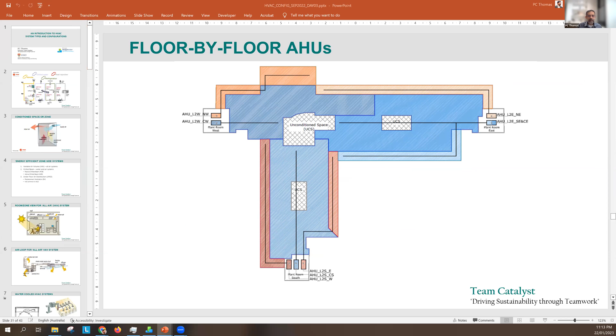If you remember what Mansi said, a summary of internal and external gains is shown in this chart. The building loads are basically solar radiation, what comes in as sunshine, and what's generated inside the building, lights, equipment, and people, which all produce heat. Then there's the temperature difference, since there's a temperature outside and you want to maintain a temperature inside, so you use U values to mitigate heat transfer. Finally, there's air exchange, including infiltration from poor quality construction that leaks, and ventilation, since you're bringing in air for people.